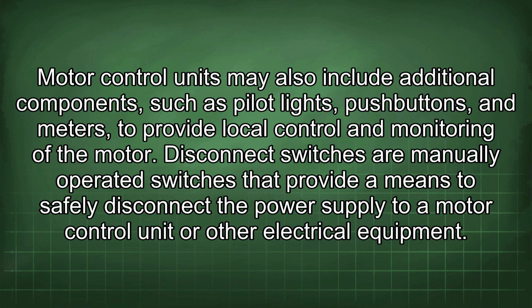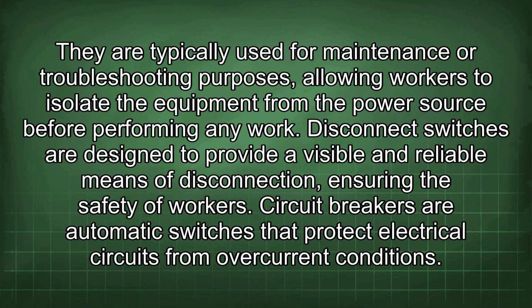Disconnect switches are manually operated switches that provide a means to safely disconnect the power supply to a motor control unit or other electrical equipment. They are typically used for maintenance or troubleshooting purposes, allowing workers to isolate the equipment from the power source before performing any work. Disconnect switches are designed to provide a visible and reliable means of disconnection, ensuring the safety of workers.